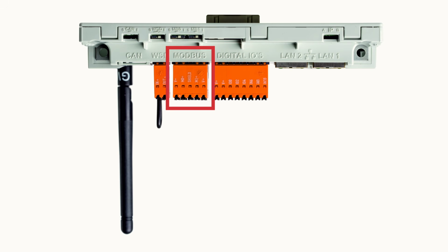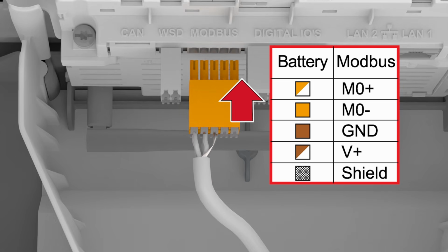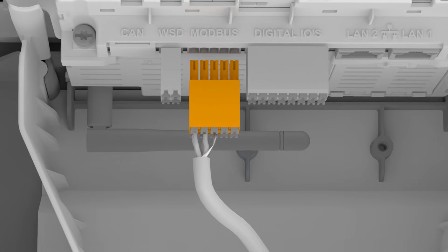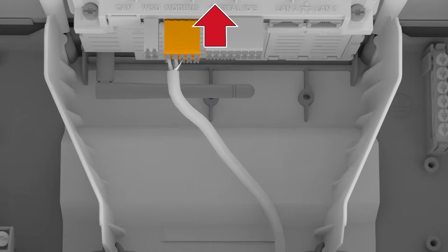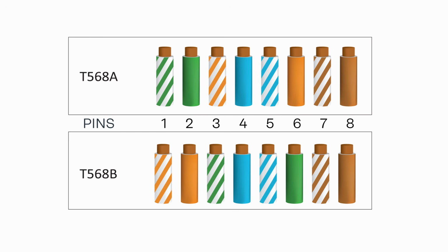However, for existing devices, you still need to cut open the wire and place the different wires directly on our Modbus plug that you find in the middle of the pilot card of the inverter. So this is this little orange plug that you see here. And with that, there comes a specialty about the cable connector, about the RJ45 clamps, meaning that there is always a standard A and standard B version. And this is very crucial.